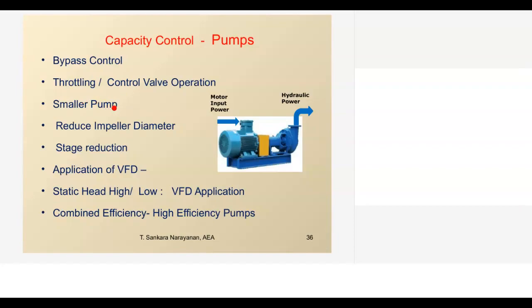Third option is, if the capacity requirement is permanently less, one can consider a small pump or trimming the impeller. So these two options will make a permanent capacity reduction for the pump. Then in a multi-stage pump, one can consider stage reduction or providing a blind in one of the stages so that we can operate on a lower head. Application of VFD will be the last stage. What I am telling, in any audit we have to explore all these potentials, then go for VFD.